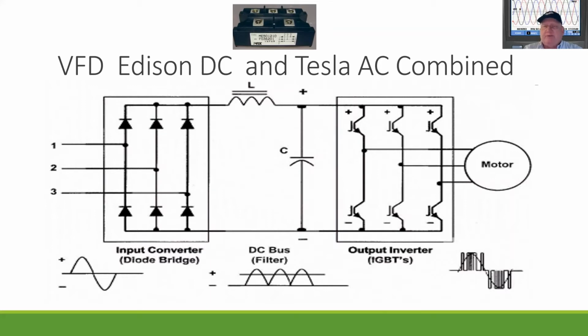And so once those devices were built, all the rest of the components of a VFD are kind of like the fluff. That's what makes it know when, how much, how it responds, how it reacts. But these are the main components that make a VFD work. Inherently, there are losses in these components. So the average VFD operates anywhere from 3% to 5% efficiency loss based on these components that are internally in the product.